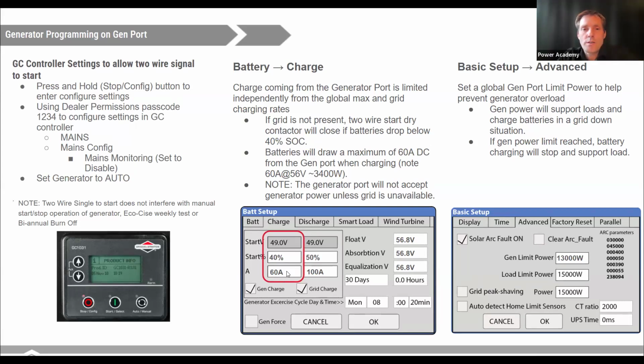Daniel, what two things does a generator power when that generator is started up by that Sol-Ark? Not only does it charge the batteries, but also takes over the loads. Yeah, so it's powering the battery charging system as well as powering the loads that are connected to the inverter. And so keep that in mind.